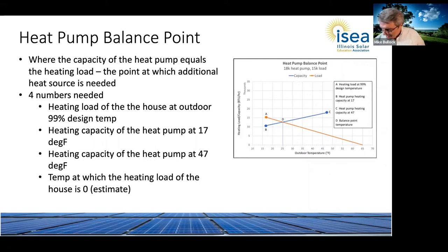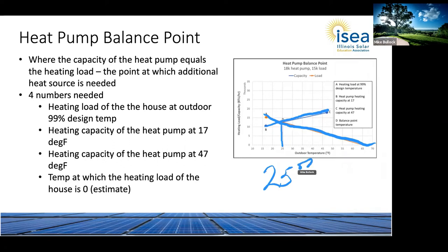So you take those points, and you see there's two lines, and where they cross, that's the balance point. That's the temperature at which the heat pump can keep up with the heat loss - it can generate enough heat to keep up with what the house is losing. Where that intersects, in this case, it's 25 degrees. So you can set the system so that when it's below 25 degrees, it switches over to the furnace.